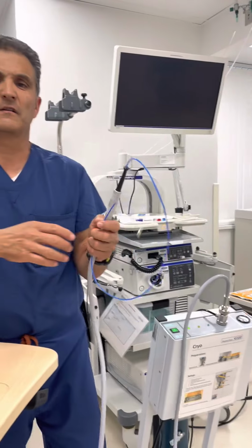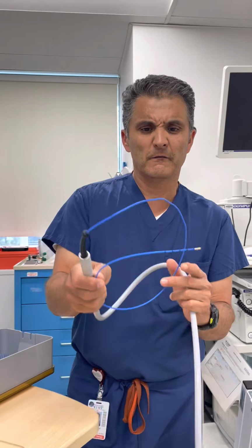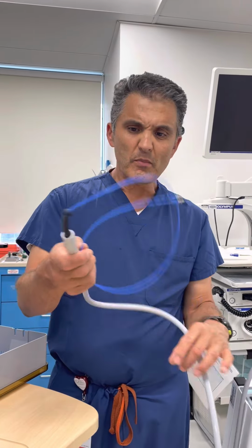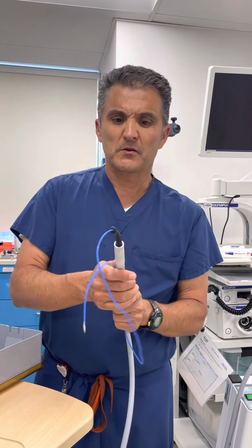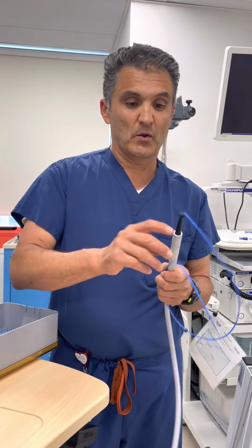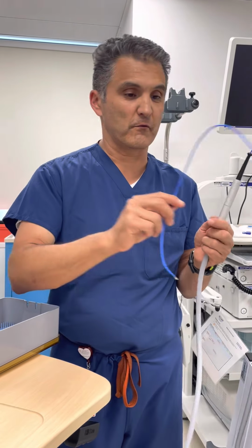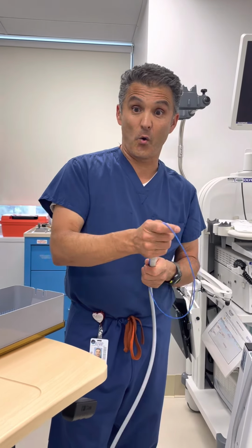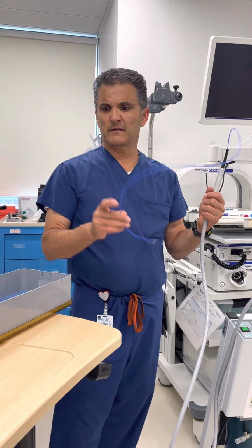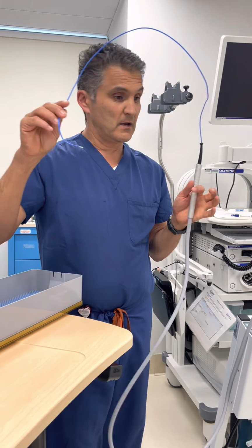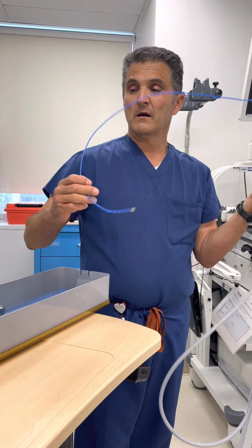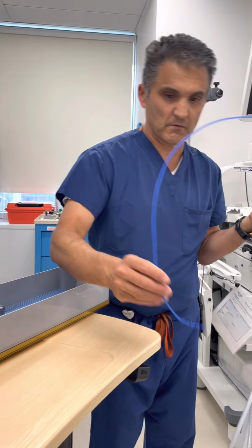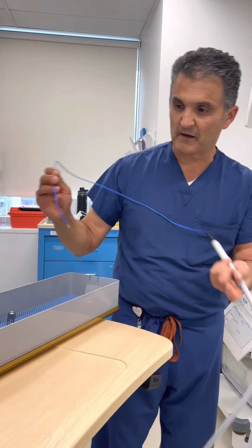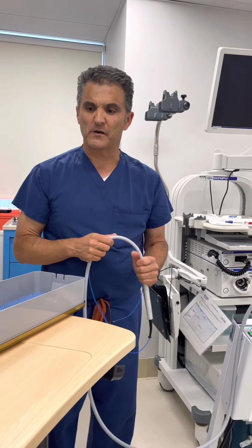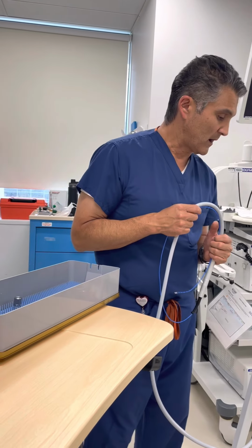One of the most common uses that we have for this device has been the removal of blood clots. It is used with our video system, utilizing a large size scope. This probe and the small one, of course, go through the large size channel of the scope. Once it's inserted, the physician will do that part, going to the object, whether it's a foreign object or blood clots, and freeze it, remove it, put it in room temperature water, extract, and repeat the same thing over and over, which is why it's important to have at least a couple of containers with saline.